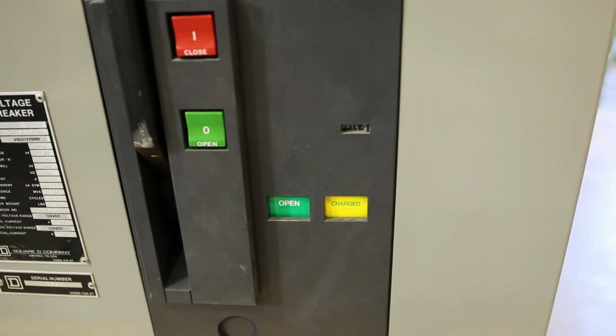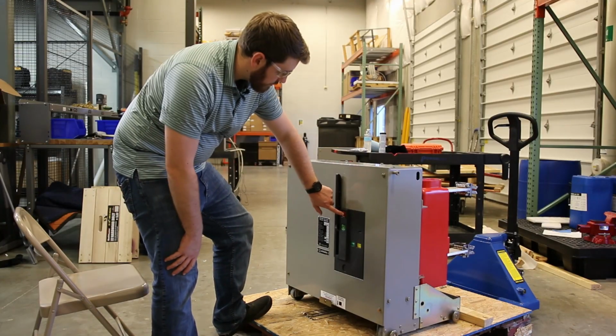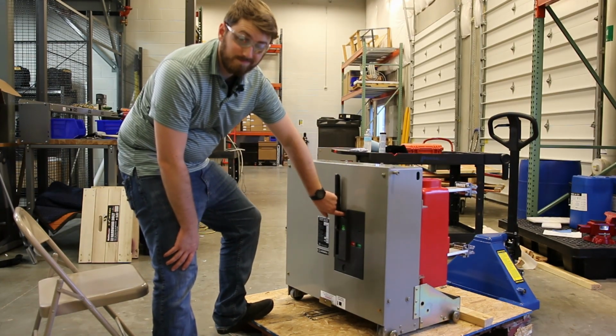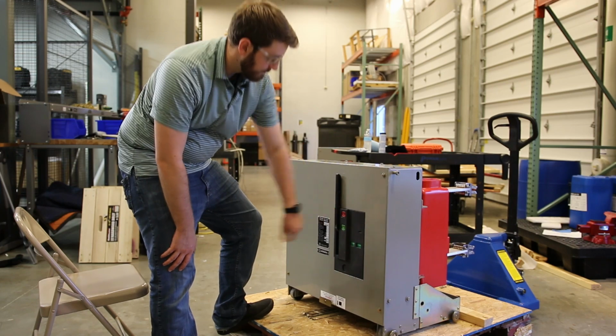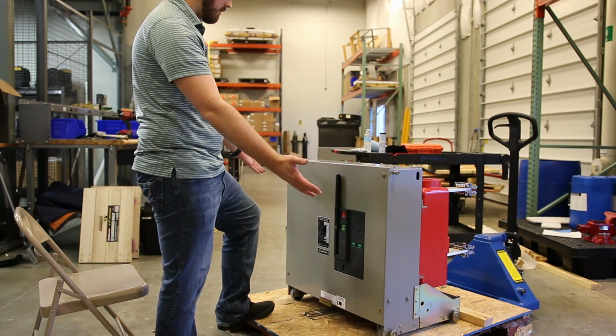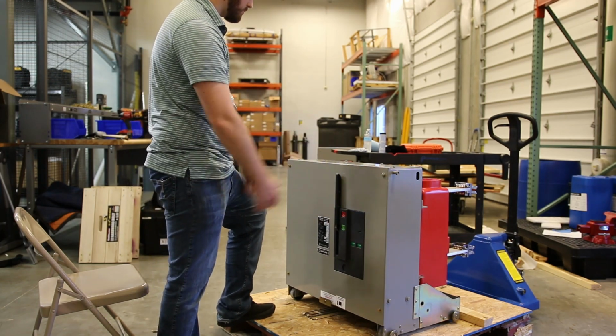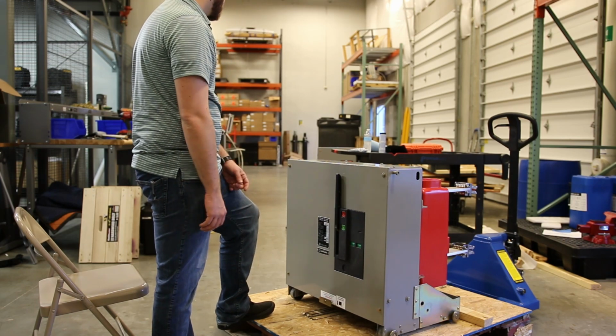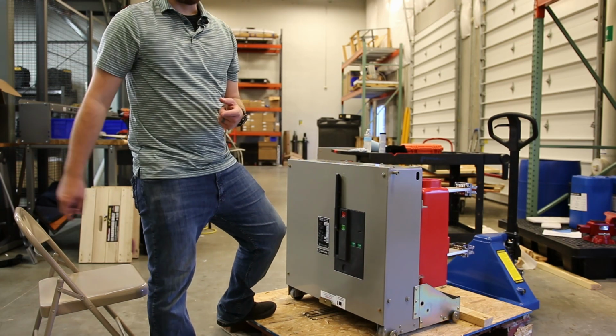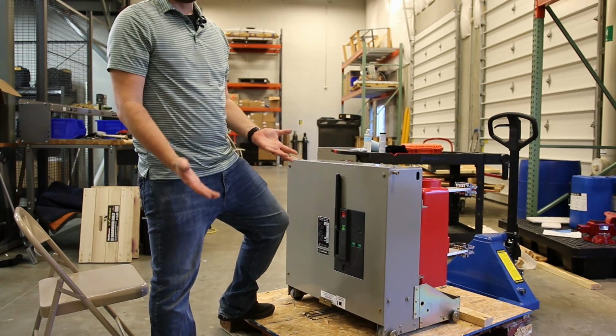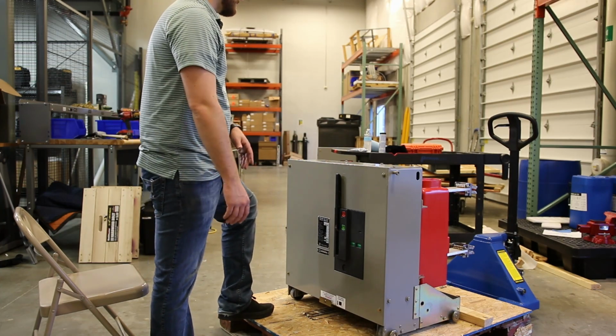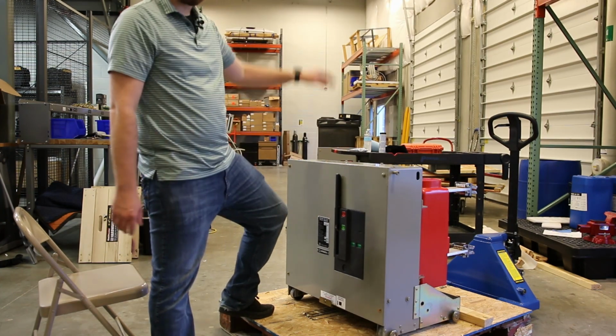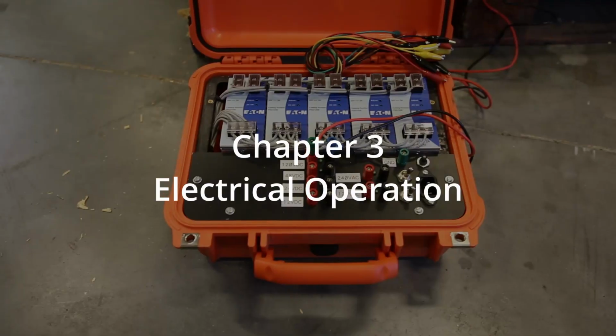We are open and charged. So with the breaker charged and open, we can go closed and open. And that's our manual test. We've used the push buttons to make it operate manually. So the next thing that I want to do, I'm lazy. I don't want to manually charge this again for the million times that I have to do this. What I'm going to do is hook up a power supply and do it automatically.